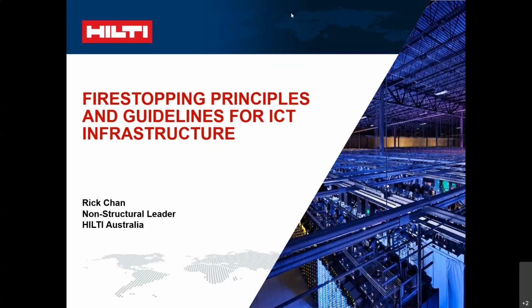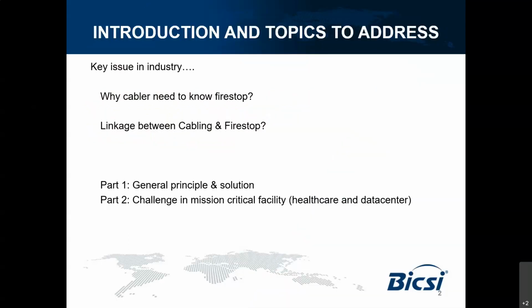To begin with, I want to show the linkage between fire stopping and cabling. As Paul already outlined, it is mandated by the building code in Australia. When we have a penetration where a cable needs to pass through certain rooms, we need to check if it's a fire rated barrier. If so, we need to do a proper seal. Paul used the point of 'break it and fix it' - I'd rather think about designing it properly from the start, rather than breaking and fixing. I hope after this presentation you'll understand why, because if we just break and fix, it could happen that there's no compliant solution available.